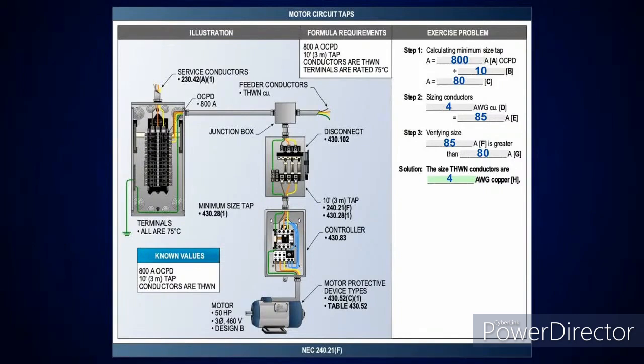Oh, looky here. Here's another one. Here's where we're doing a tap. We're going down to a motor here. Okay? It's 10 foot or less. What do I divide by? 10. If this was 25 foot, I'd take it at a third. So in this case, it was 10 foot or less. Divide by 10 gives you 80 amps.